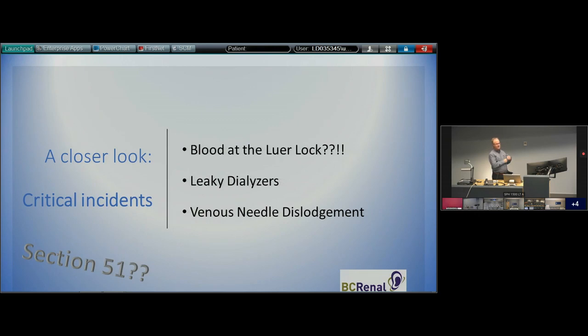Turns out, at the end of it all, as best as we could tell, it was not blood. It was corroded metal. And the learning from that, apart from how to work our way through a critical incident, was also that we had to work with the vendor and call them up and say, how come your parts are corroding? And they said, well, you're not washing them properly. And we said, well, how are we supposed to wash them properly if we can't get them wet? And they said, oh, well. So it allowed this facility to have a meaningful conversation with the vendor about how to improve what's going on with the machine.